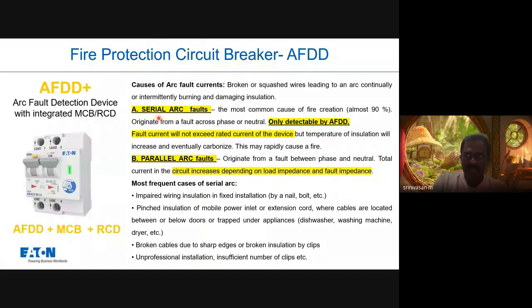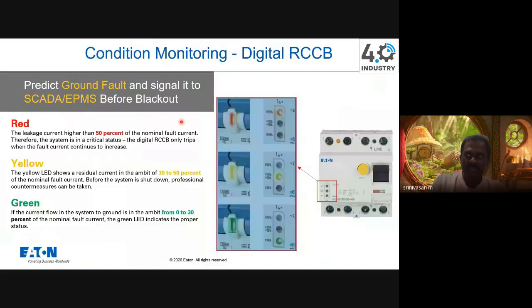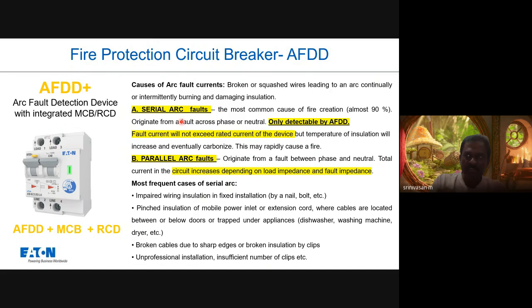Normally, if the arc is happening in any phase conductor, like a serial arc, the fault current will not exceed your MCB rating. For example, if I have a 10 amp MCB and a serial arc is happening in the phase wire, the fault current will not go more than 10 amps. So the MCB will not trip for the arc. The MCB will trip only when the arc becomes bigger and leads to insulation failure, and it goes to a short circuit. But by having this arc fault detection device, when the arc is at a very initial stage itself, it is detected by the AFDD and it clears the fault.